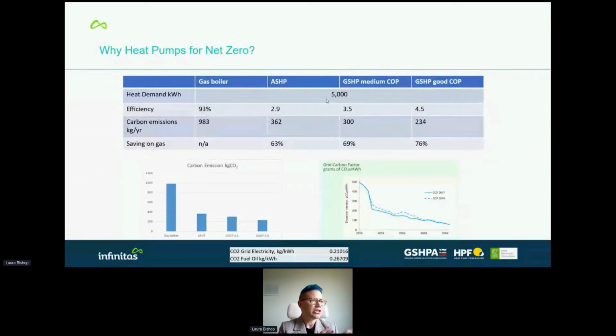kilograms per year. As you move across to ground source, which tends to have higher COPs because the temperature you're bringing into the heat pump is higher because it's coming from the ground rather than the air, your carbon emissions start to reduce even further. So from a baseline of gas, 983 kilograms per year, you can see on that bottom line there that straight away moving to an air source, you're saving about 63% of carbon emissions per year, and a ground source heat pump with a good COP of 4.5, about 3/4 of the carbon emissions from this particular building can be saved by using a heat pump. And that's just shown here in this little graph at the bottom.